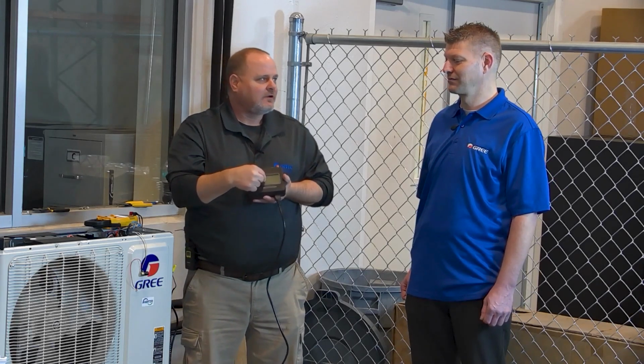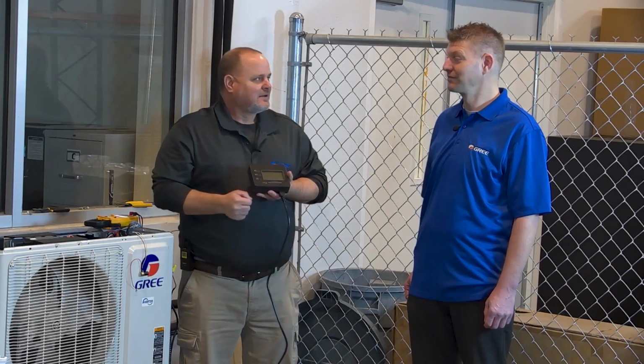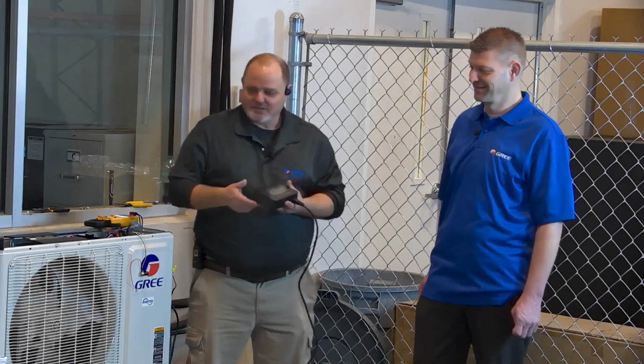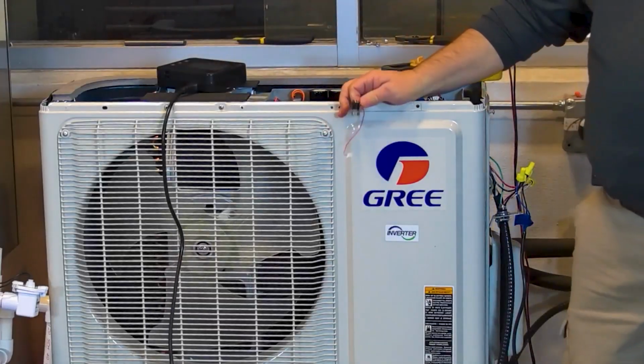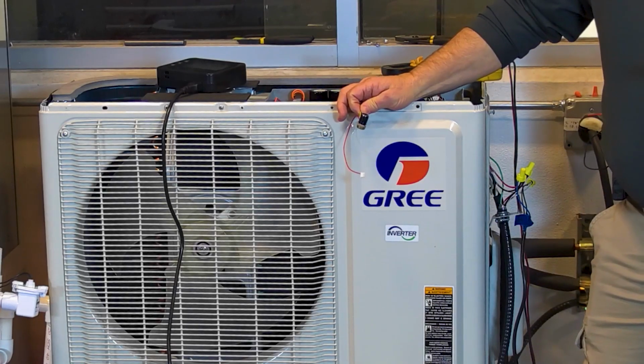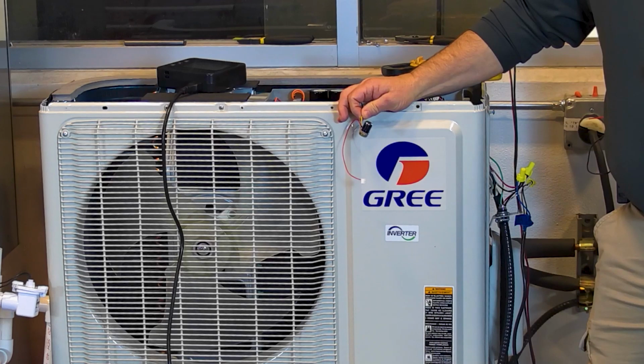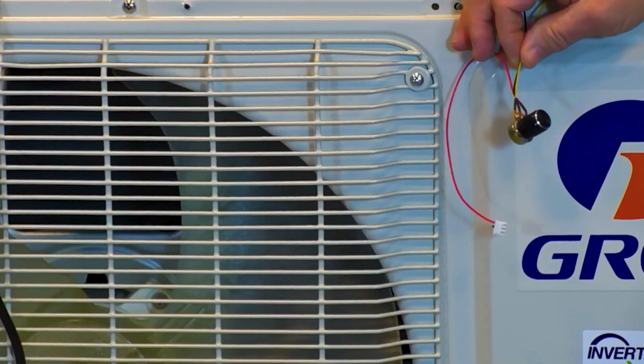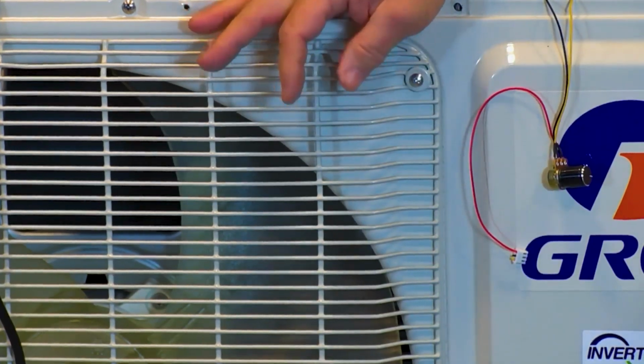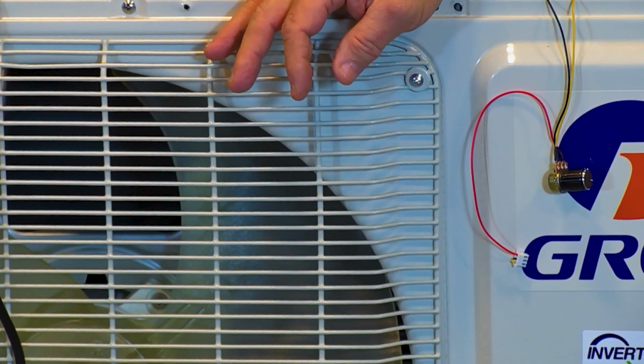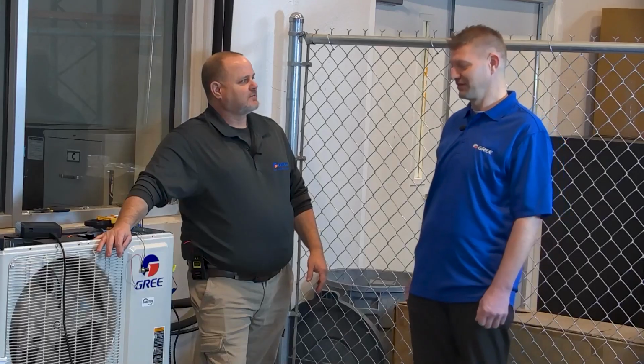But you know what also is going to know? This machine. It's going to tell you, hey, no, you can't do that. How do I know? That's a rheostat. JD and I were playing. We hooked it up. We set this thing to specifically 50K, which is a 50K thermistor. We said the discharge thermistor is 50K, right? Yep. What did we end up with when we ran it for a little while? An E1 or an E4? It was E4. E4, yeah. Because of discharge temperature. Yep.